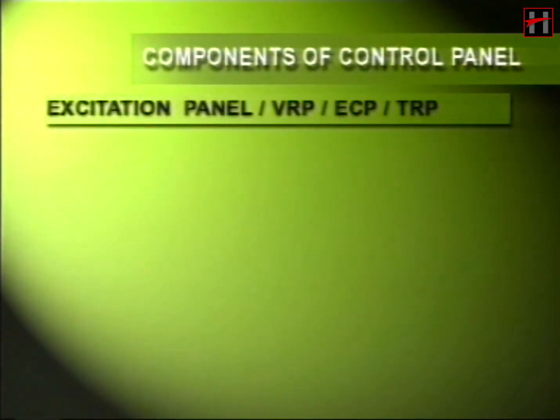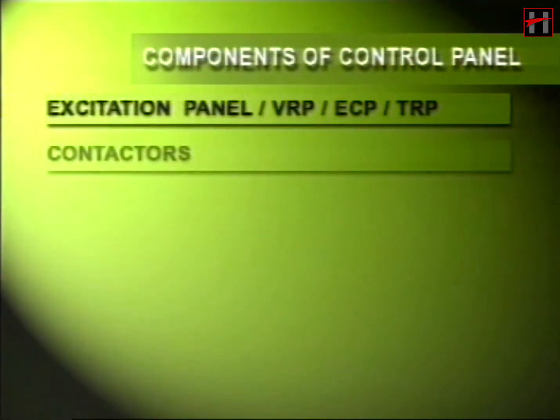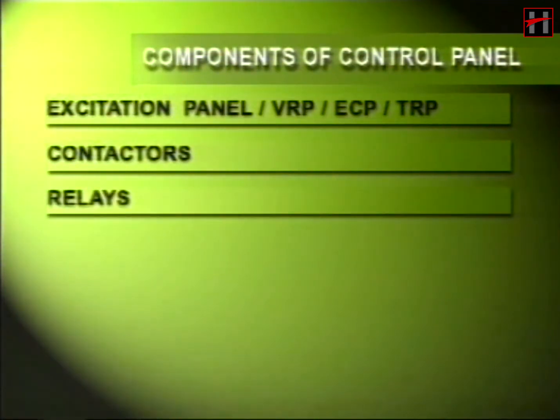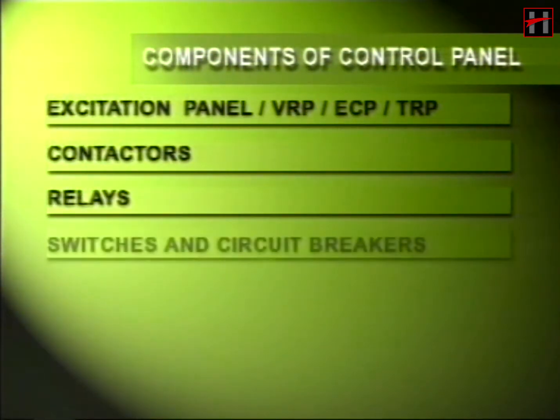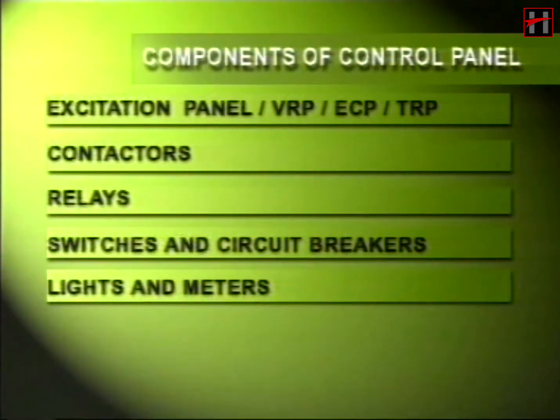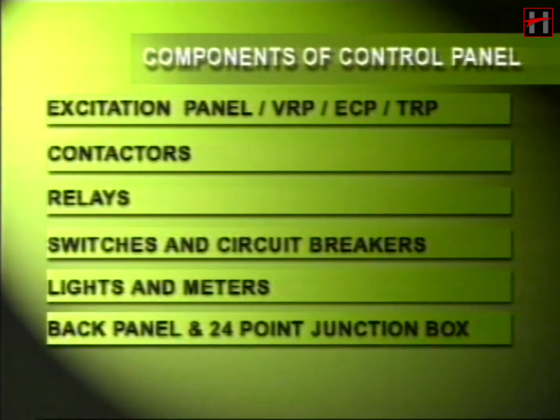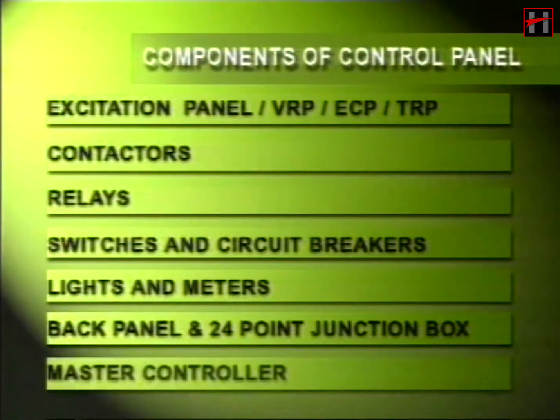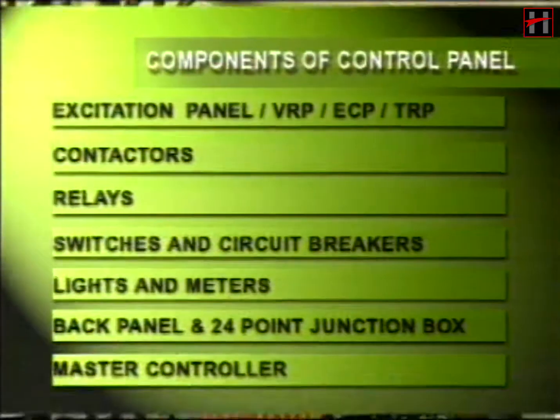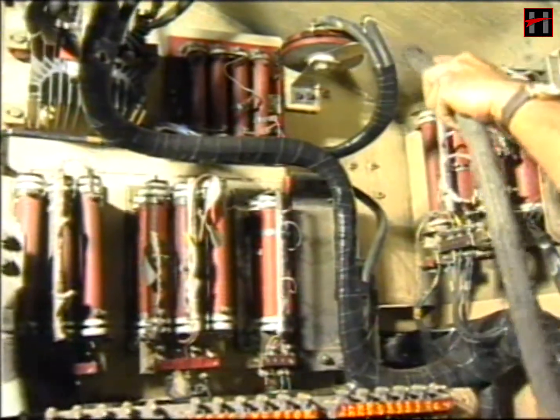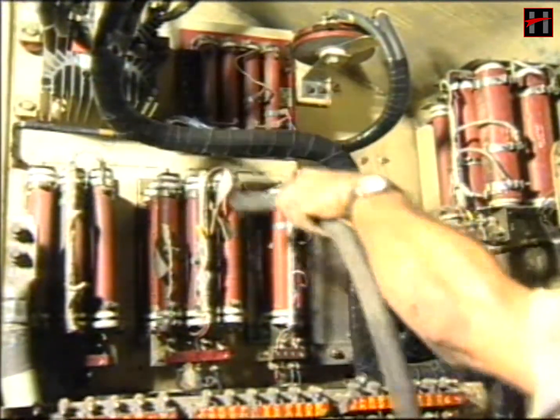The various components of the control panel are the excitation panel, voltage regulator panel, engine control panel, etc., contactors, relays, switches and circuit breakers, lights and the meters, back panel and 24-point junction box, and the master controller. Before beginning servicing of the control panel, clean with lintless cloth and air blow all the loose dust and dirt from all the components of the control panel.